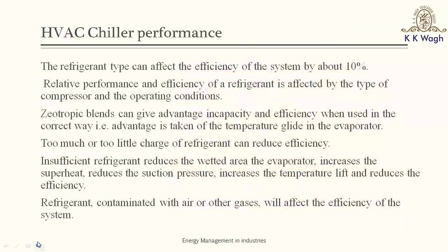On the refrigerant side, there are other things to be kept in mind, and I just quoted some figures. For example, appropriate selection of the refrigerant type, which I was mentioning, can affect the efficiency of the system by about 10%. Then the relative performance and efficiency of the refrigerant is also affected by the choice of compressor and the operating conditions. This you would better understand with the help of p-h diagrams, pressure-enthalpy diagrams. And I also mentioned that appropriate charging of the refrigerant is essential. If there is too much charge, that would also reduce the coefficient of performance, and too little a charge is not at all advisable. That is going to impact the efficiency adversely.